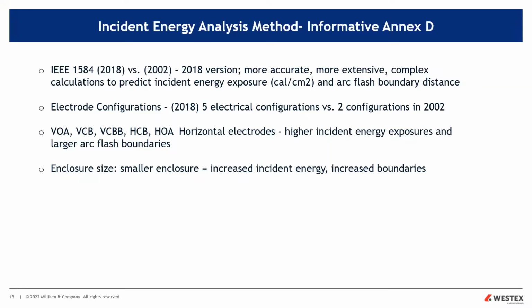The last one was 2002. So the 2018 is a better version. It's more accurate, more extensive. Now there are more complex calculations, but it gives you more accurate predictions on incident energies and arc flash boundary distances, which is what we're looking for. So why is it better? Well, there are a lot of reasons, but some of the key ones are the electrode configurations. In the 2018, there are 5 electrode configurations; in 2002, there were only 2.